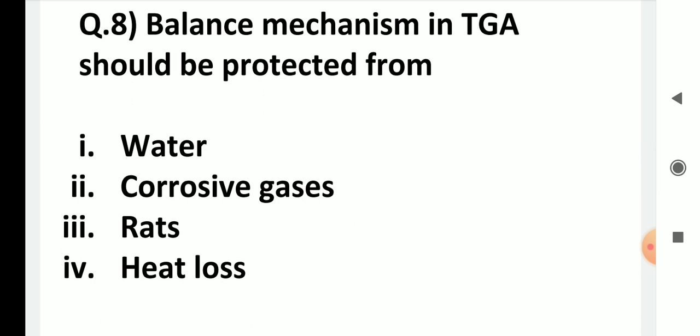Balance mechanisms in TGA should be protected from: water, corrosive gases, rats, or heat loss? The right answer is corrosive gases, because corrosive gases will damage the mechanism of the balance.